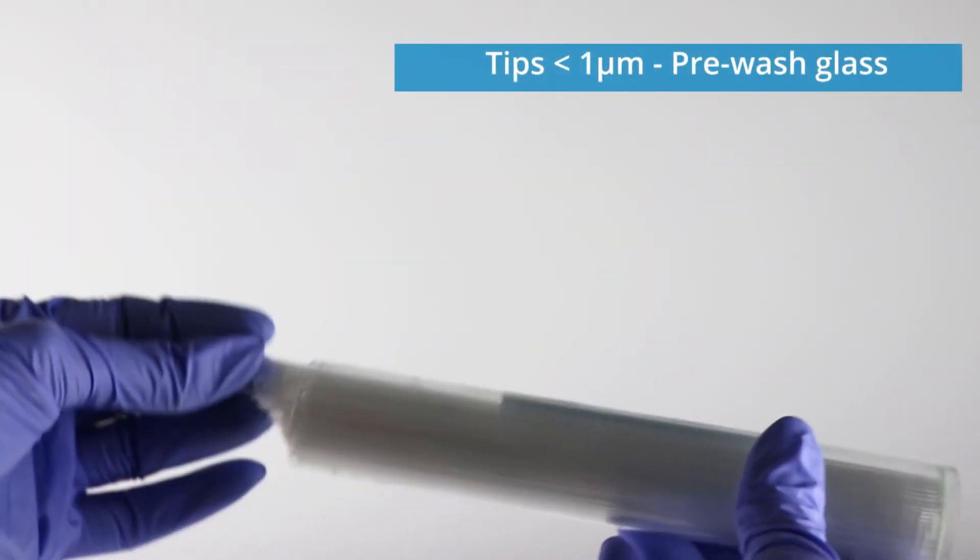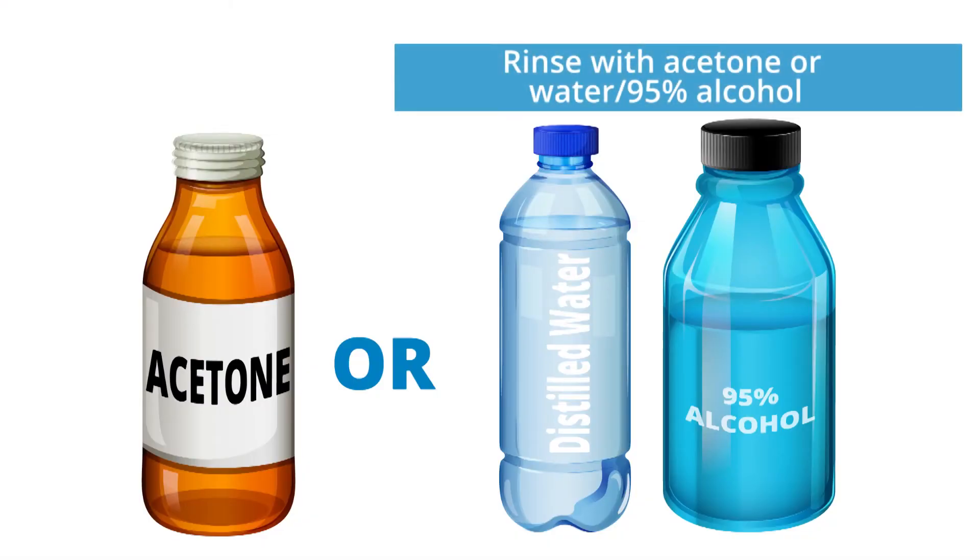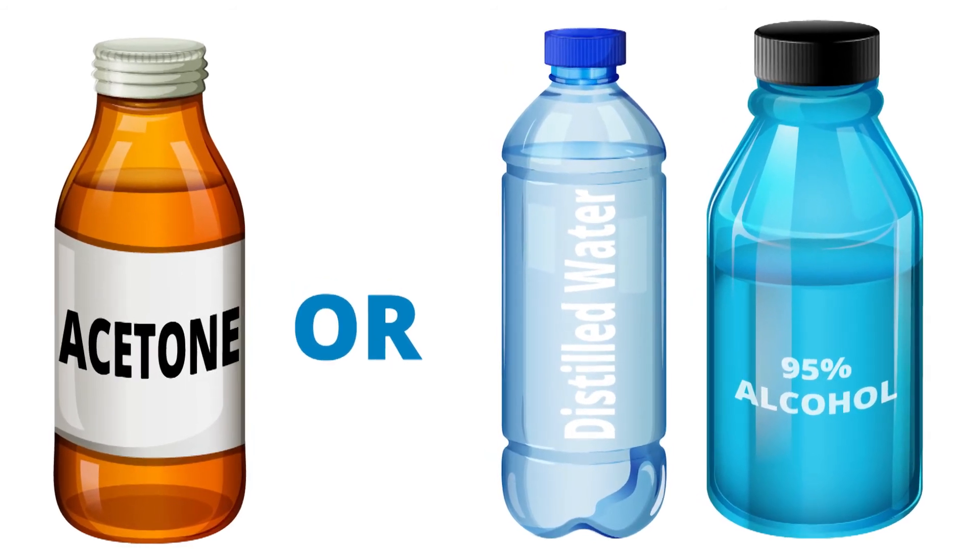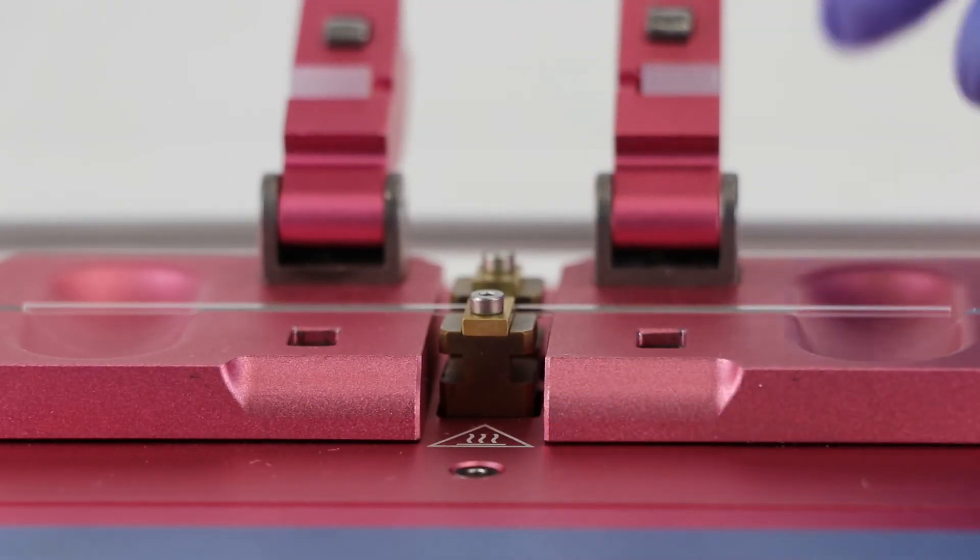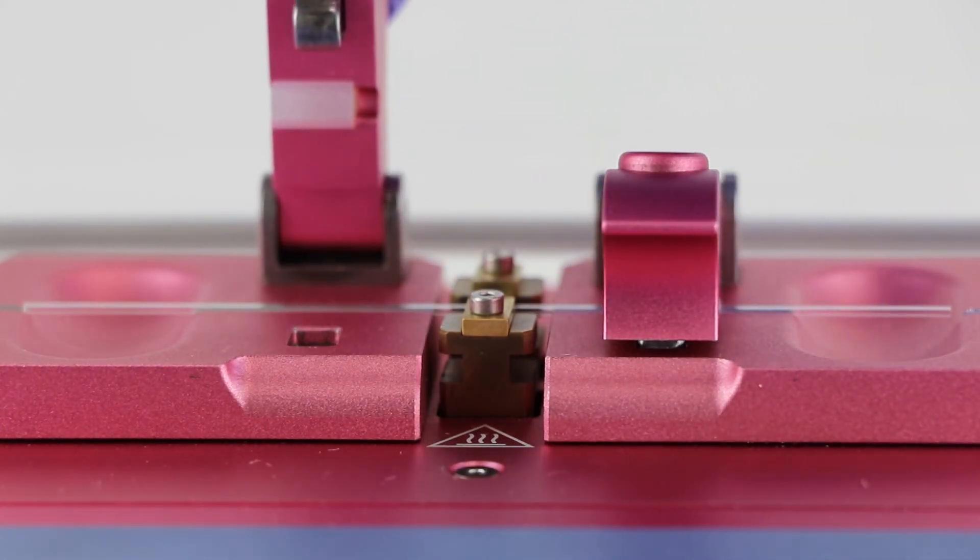When pulling glass tips finer than one micron, first wash the glass capillaries in filtered acetone or filtered distilled water with 95% alcohol. Then allow the fluids to evaporate in a clean and dust-free environment. This assures that the submicron tips are not immediately clogged with glass particles from the manufacturing of the capillaries.